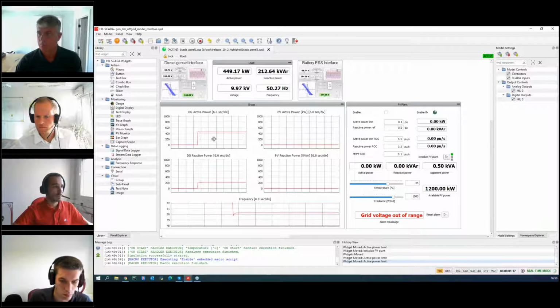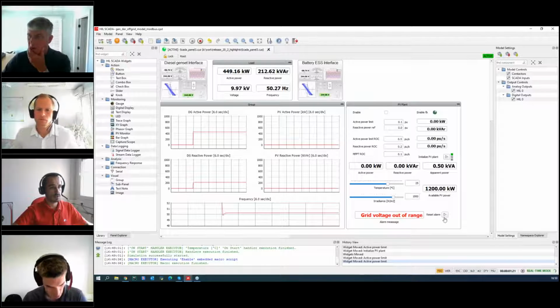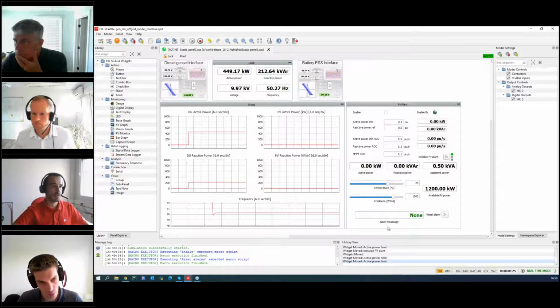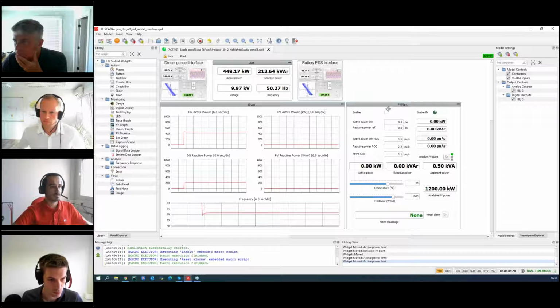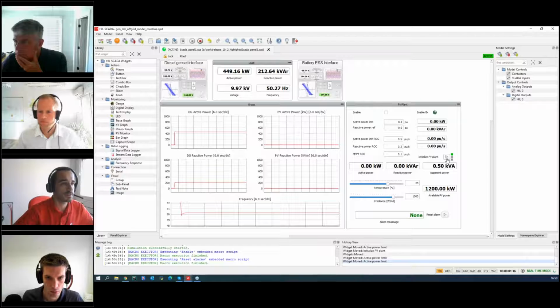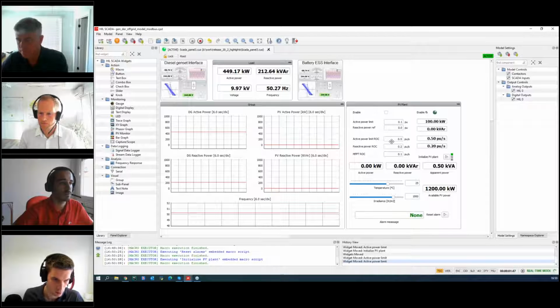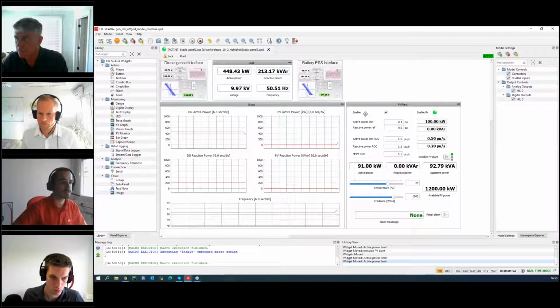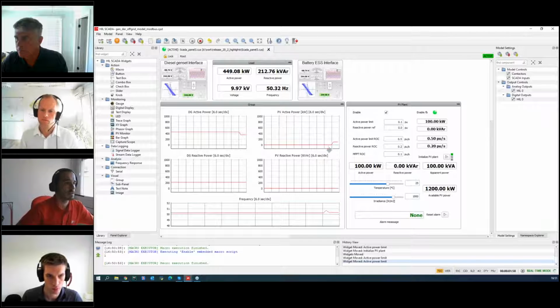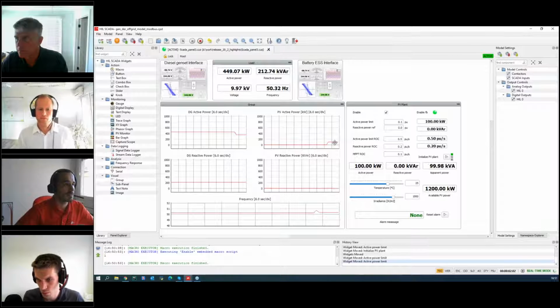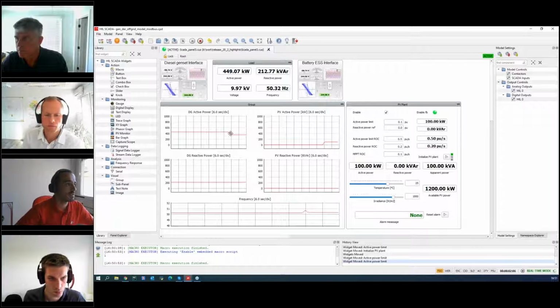Now we have a voltage that is built from this diesel genset. We can reset the alarm here, and now we don't have that fault anymore, and the PV plant can be started. Because this uses communication, I will first initialize the registers inside the Modbus server with the values already presented here. Now we have valid values for rate of change, references and so on. Let's start the PV plant. I'm enabling it, and now we can see how the power increased on the PV. PV active power increased, and this induced the diesel genset to support less of the load.